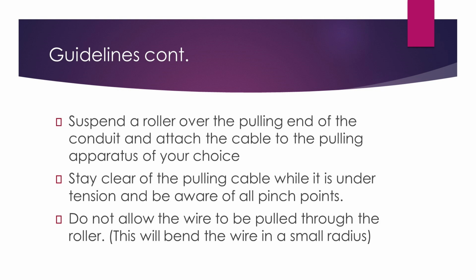Of course, put your roller over the conduit that you're pulling. That helps keep it from hitting the edge of the conduit and skinning any insulation off the conductor. Stay clear of it—if it's under tension, avoid all pinch points, and do not allow the wire to pull through the roller itself. That's too much of a bend radius. Also keep your fingers and hands clear of that kind of stuff; you don't want to get pulled through that roller.